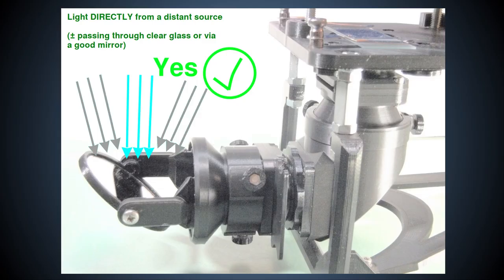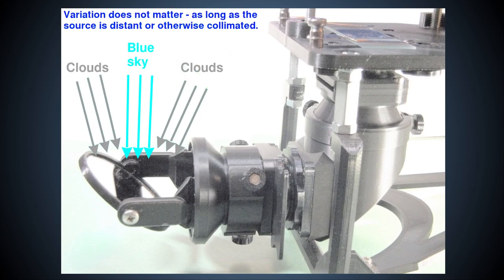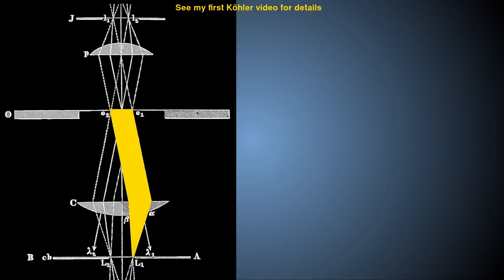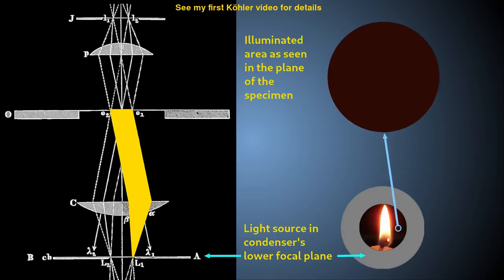When using natural daylight in the correct way, it doesn't matter for most ordinary uses of the microscope if the light contains some variation in brightness across the field, such as a combination of clouds and blue sky, or the features of some faraway landscape, because the Köhler principle will even out this illumination in the specimen plane.